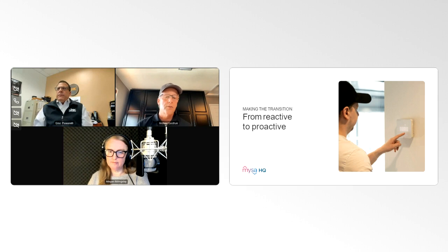And with remote management, it really helps you prevent excess wear and tear by keeping set points in check and using setbacks during unoccupied periods. When you have that visibility, you can better understand how the HVAC system is working, what components are potentially degrading over time, and if something that was working fine yesterday may all of a sudden not be working correctly today, you can see that based on the runtime reports.